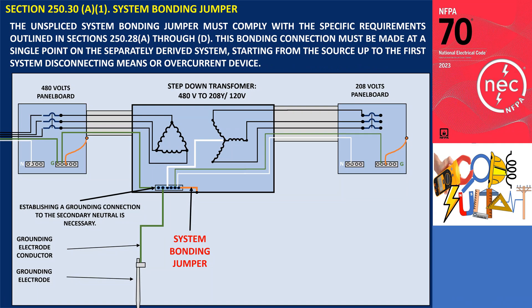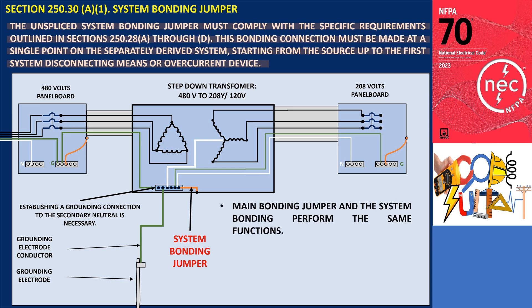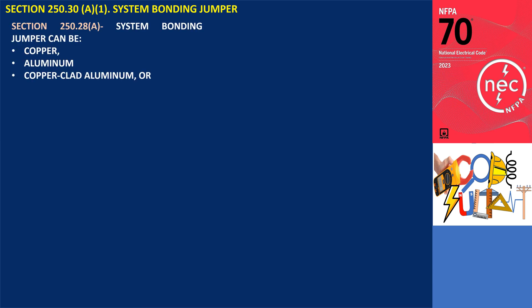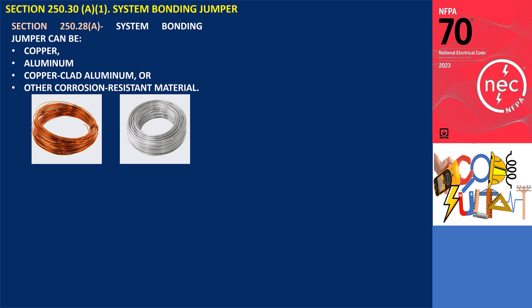The unspliced system bonding jumper must comply with the specific requirements outlined in sections 250.28 A through D. This bonding connection must be made at a single point on the separately derived system, starting from the source up to the first system disconnecting means or overcurrent device. Since the main bonding jumper and the system bonding jumper perform the same function, the system bonding must comply with the requirements specified in sections 250.28 A through D. According to section 250.28 A, the system bonding jumper must be made of copper, aluminum, copper-clad aluminum, or other corrosion-resistant material.